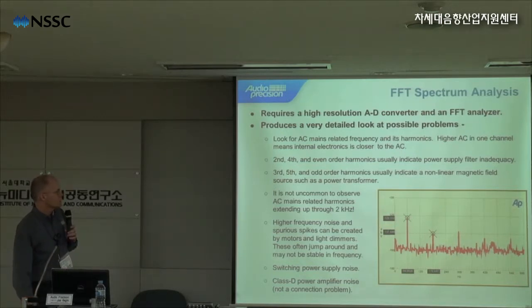So with spectrum analysis, we can get a very detailed look at possible problems. You can look for AC mains related frequency and its harmonics. A higher AC level in one channel means the internal electronics is closer to the AC source. And you can look for second, fourth, and even order harmonics, which usually indicate a power supply filter inadequacy. Those would be the even orders. The odd orders, third, fifth, and higher, usually indicate a nonlinear magnetic field such as a power transformer.